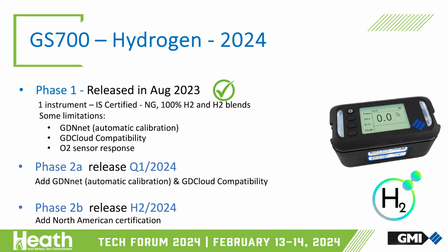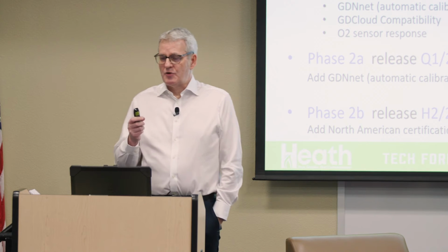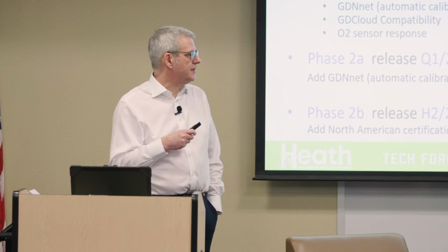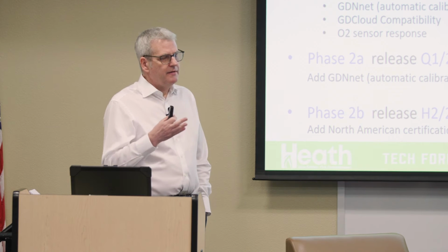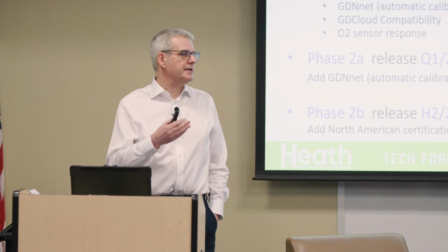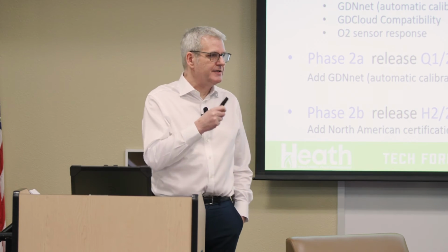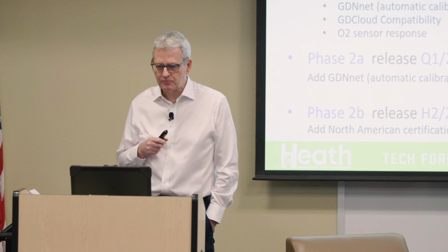So just to summarise for this instrument, yes, it was released last year. It is intrinsically safe. What we do have, however, is that the intrinsic safety is IECEx or ATEX, so that's a European type certification. However, having spoken to many of you in here and other utilities in the Americas, the ATEX certification is acceptable just now. Yes, of course, we'll work on UL and CSA, but having the intrinsic safety certification ticks the boxes just now to allow certain trials to commence.